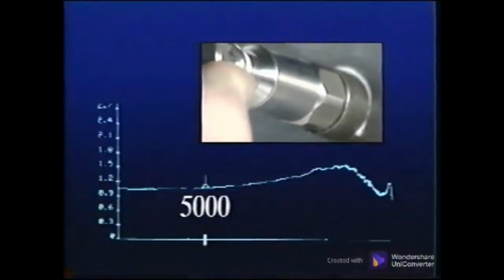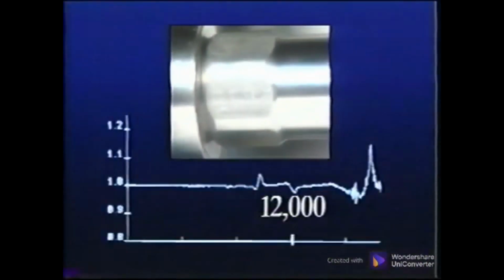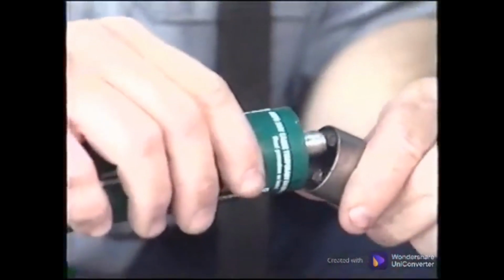Using a coupling fluid between the magnet and sensor and magnet and machine can increase this up to 5,000 Hz. This is still only one-third the needed range to acquire information around one times gear mesh. A threaded stud mounting with a coupling fluid can increase this range by at least two times. Fortunately, not all gear drives have such high frequencies that must be monitored.